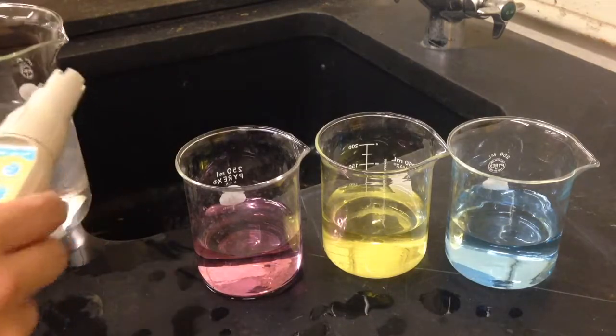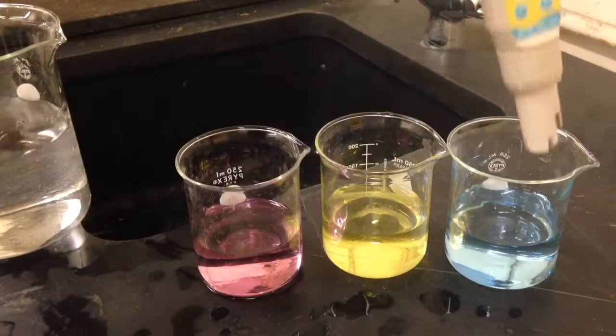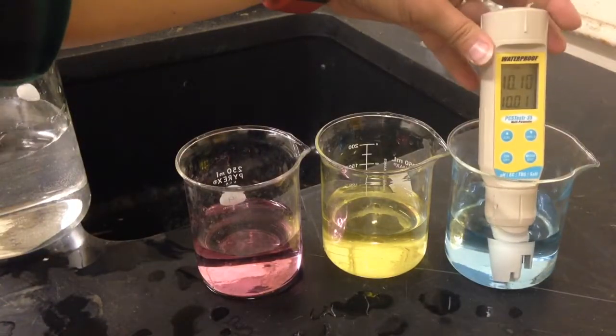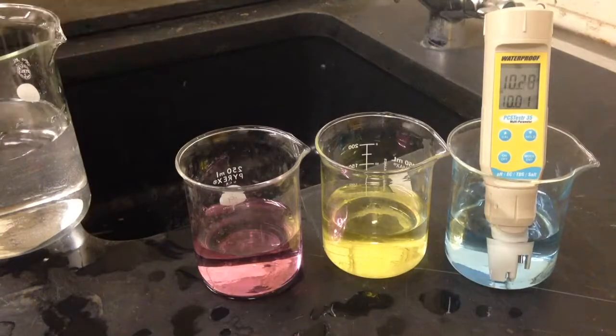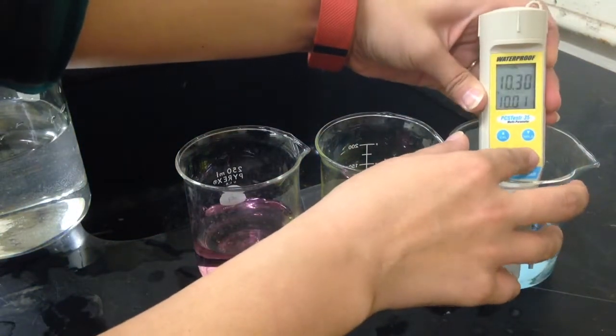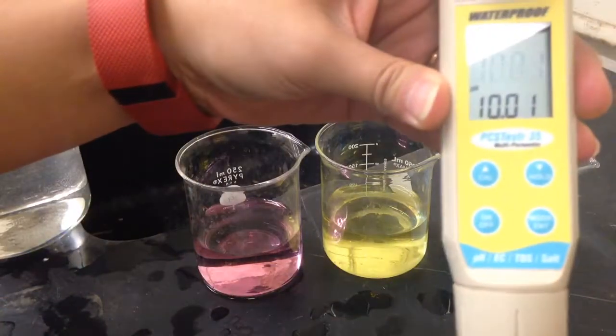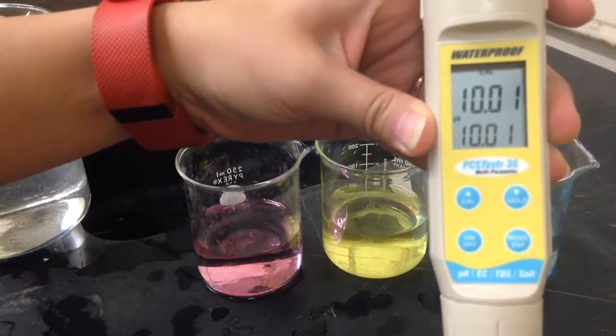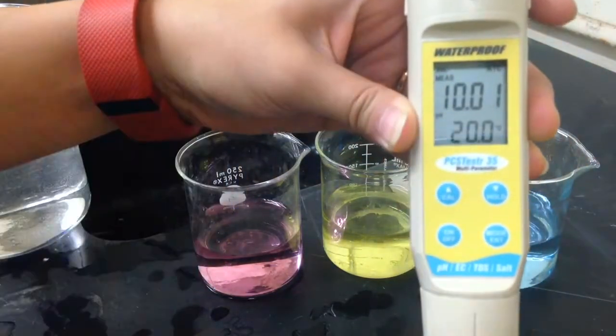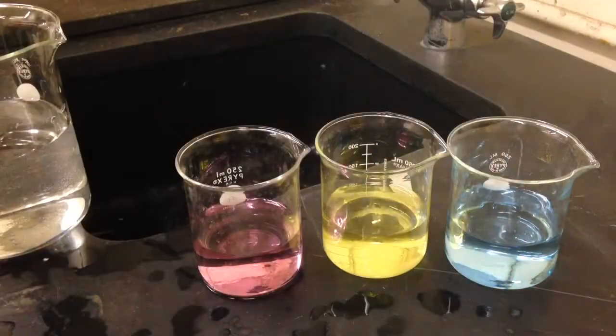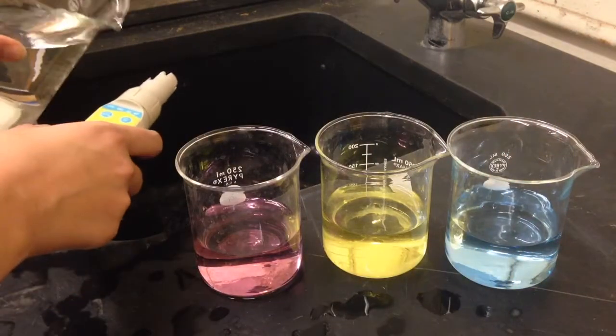After rinsing our meter, we will immerse it in the final calibration standard and wait for the primary display to stabilize. When the primary display has stabilized, we will push the Mode Enter button. The primary display will flash, and our meter will return to measurement mode. We can rinse our meter once more.